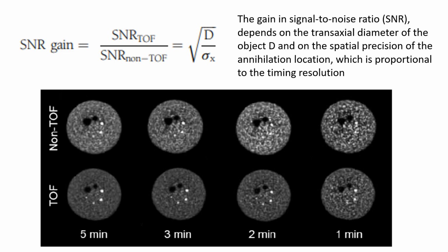Time-of-flight correction makes the system more efficient, and less statistics is needed to reach a good image quality or better lesion detectability. Here is the cylindrical phantom with 4 hot spheres with decreasing diameters positioned clockwise and 2 bigger cold spheres, and the comparison between TOF corrected and not corrected images shows significant improvements, also with very low acquisition time.